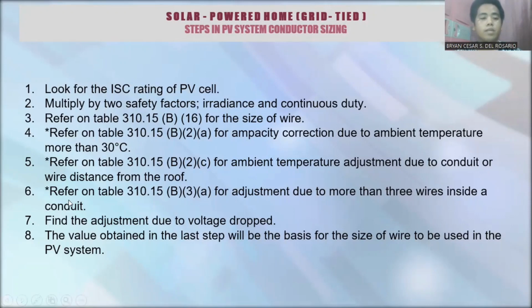Step 6, refer to table 310.15(B)(3)(a) for the adjustment due to more than 3 wires inside the conduit. Step 7, find the adjustment due to voltage drop. Step 8, the value obtained in the last step will be the basis for the size of wire to be used in the PV system. So now let's compute which wire is the right one to use.